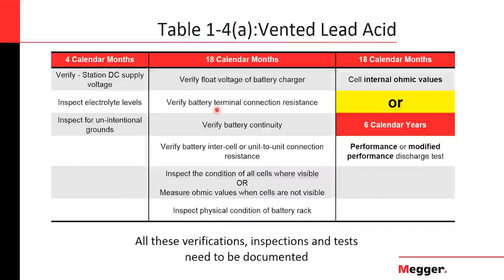So DC battery systems are floating systems. They are not supposed to be grounded. Any ground in the system will cause current circulation, which means that the battery is operating, and this is not good for the battery. Batteries in substation applications are meant to be sitting there. They don't like to work. They're just there for very special occasions. So you don't want the battery to be draining current through ground. So this should be inspected.